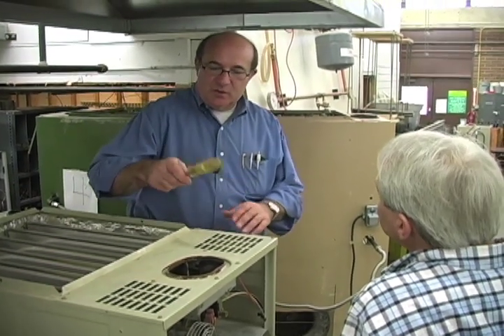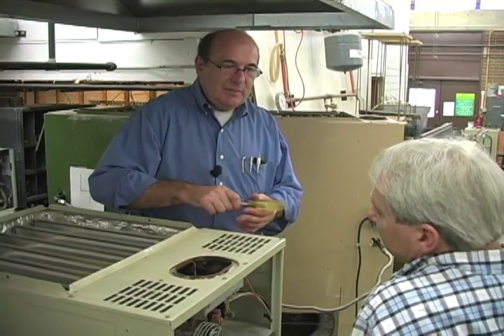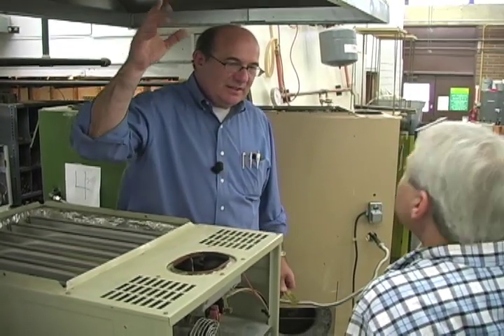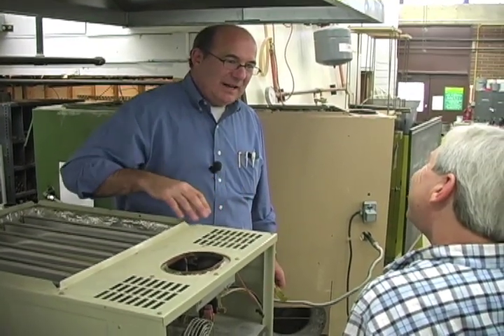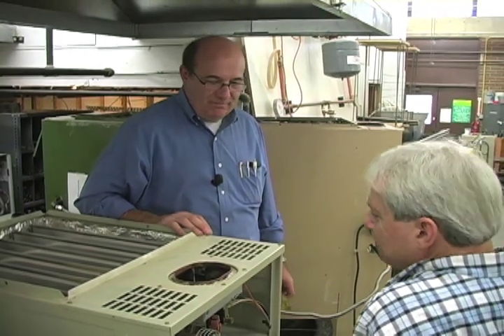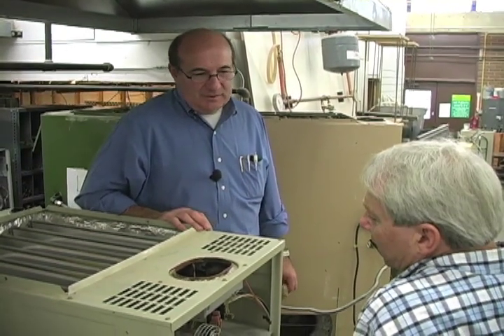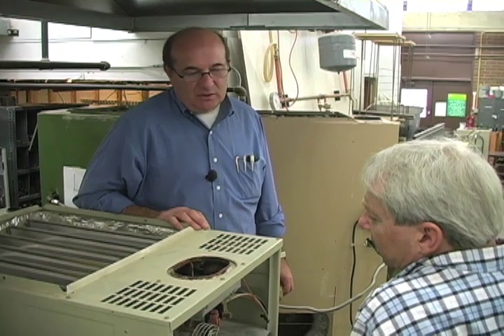On older furnaces like this old gravity exhaust or atmospheric burner, one thing an inspector might want to do is just go over to that exhaust pipe and tap it a couple of times with the back of a screwdriver. See if you can hear that material filtering back down. Good idea. Rust coming off the inside of the pipe. You'll know that you've got a potential problem with a corroded flue.